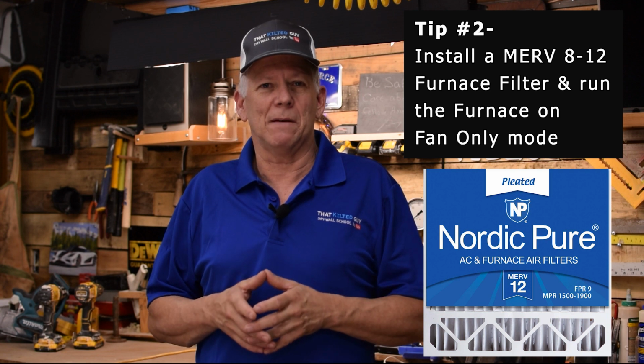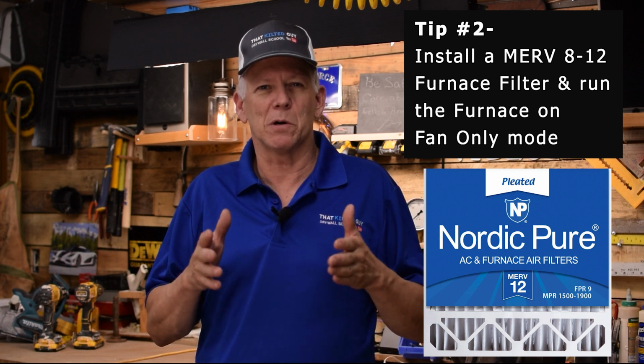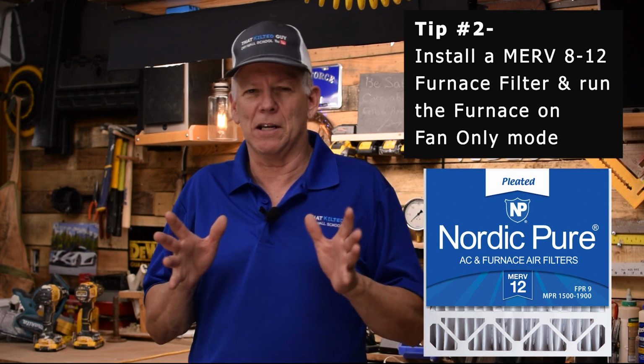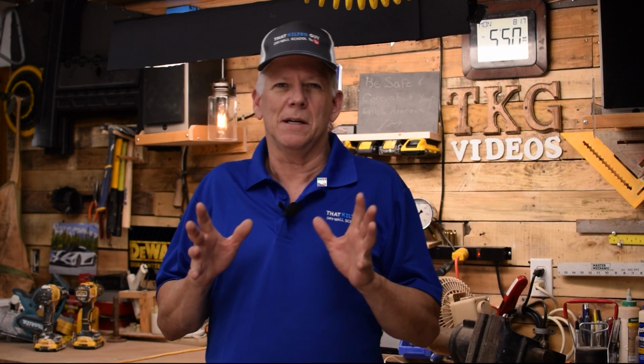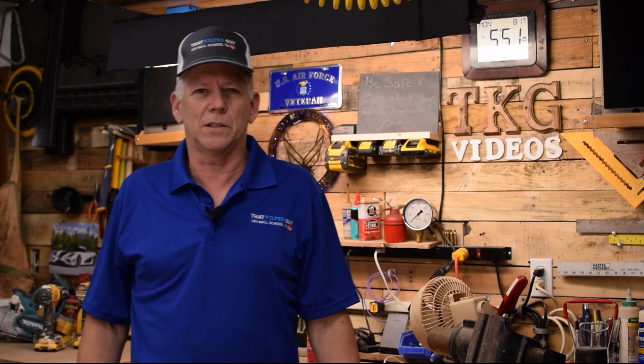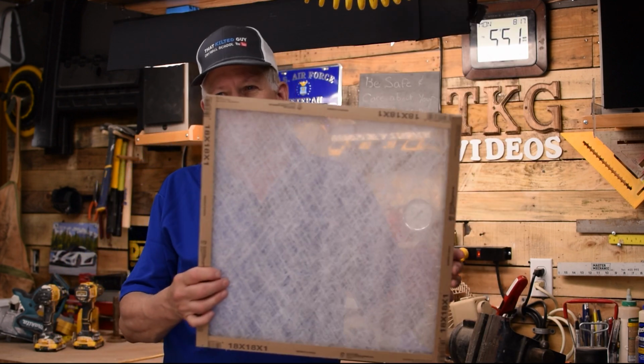If you do, I recommend you go out and get a high quality furnace filter, especially for this time. Like you might want to get a filter that's rated a Merv 8 or higher. Don't go too high. Now let me explain why. If you look on the package, it'll often tell you what it'll filter out. Now from what I've been able to gather, you need at least Merv 8. That's a rating system. And if not that, sometimes they list it like 1,000 or 1,500. Just look on there and try and get one that's rated higher, because you want a good filter. You don't want one of these.